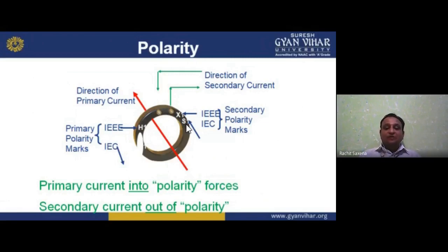Primary current into the polarity forces, secondary current out of the polarity forces. Primary current goes into the polarity and secondary current comes out of the polarity. So we can say the primary is in and the secondary is out. So primary current into the polarity and secondary current out of the polarity. So I hope you understand this.